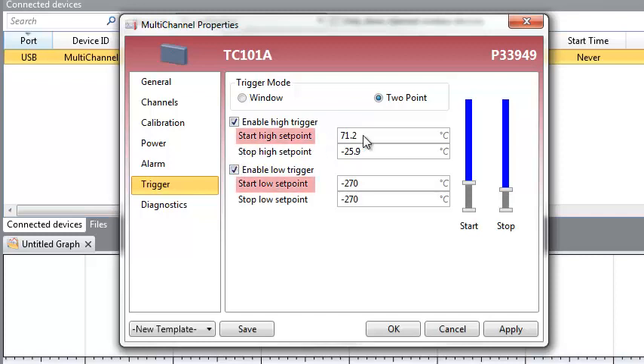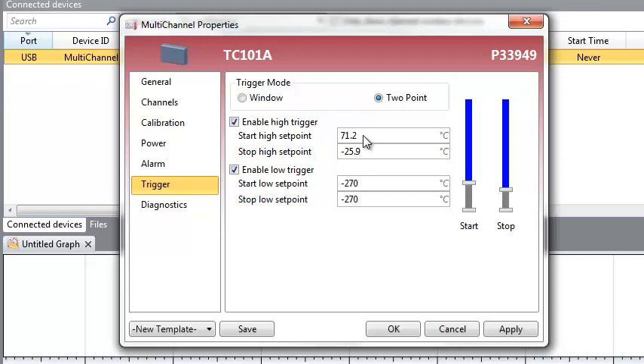The start setpoint indicates when recording begins. A reading must be above the start high setpoint value or below the start low setpoint value to begin recording. The stop setpoint indicates when recording ends. A reading must be above the stop low setpoint value or below the stop high setpoint value to end recording.